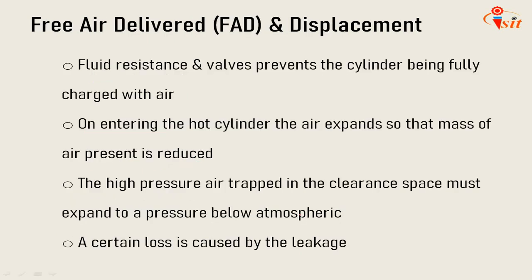Next is about the free air delivered. Commonly it is asked in the question paper. Many question papers ask about the free air delivered, that is FAD, and displacement. Now what is free air delivered? FAD is the actual volume delivered at the static pressure reduced to intake temperature and pressure, and that is expressed in meter cube per minute. And the displacement is the actual volume in meter cube per minute swept out per minute by the low pressure piston during the suction stroke.